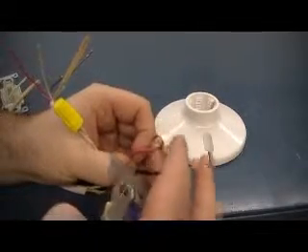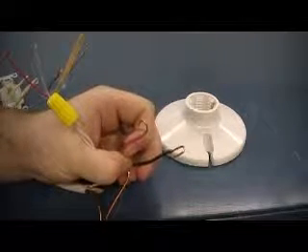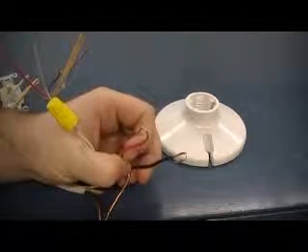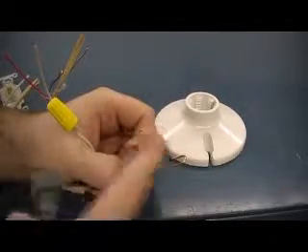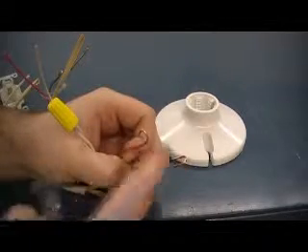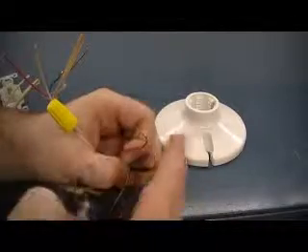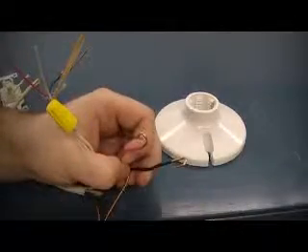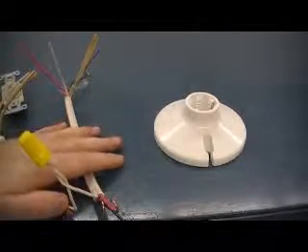These two wires are called travelers. Okay, and that's the term used when looking at three-way switches and even four-way switches. Okay, because they're not always hot. One of them will be, but not the other, and it'll flip back and forth, or travel back and forth on these two wires. Okay, so that's how you connect your first three-way switch.